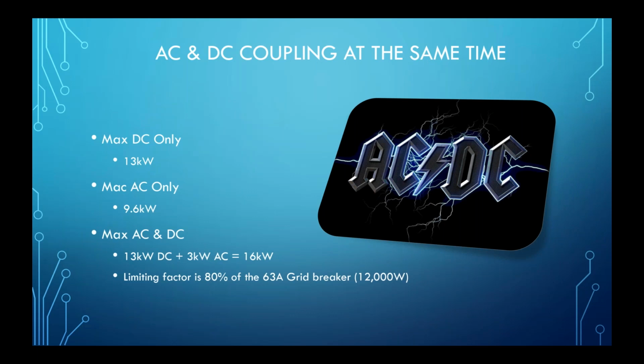Now, you can do both at the same time. The limit there, let's say you bring in 13 kilowatts of DC, you could also have 3 kilowatts of AC coming in for 16 kilowatts total. And the factor there, as the last bullet shows, is just the 80% rule of the 63 amp grid breaker, which is going to settle you back down to 12,000 watts. But you can AC couple and DC couple at the same time. The max is up to the 16 kilowatts as shown here.